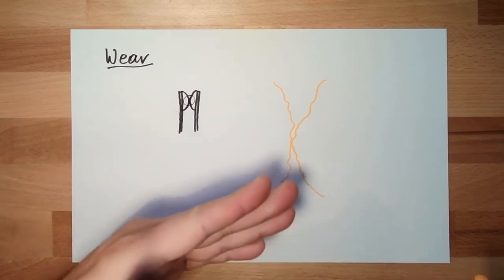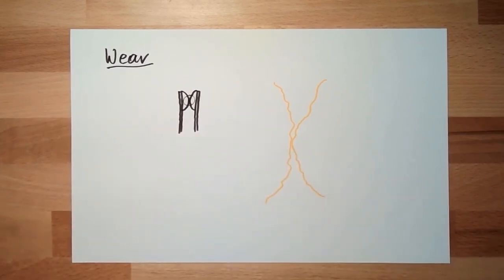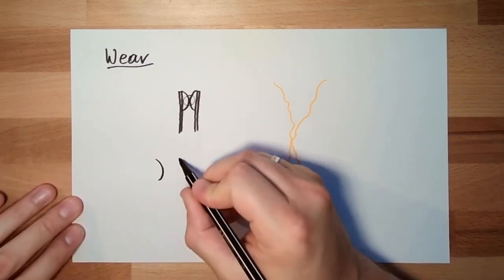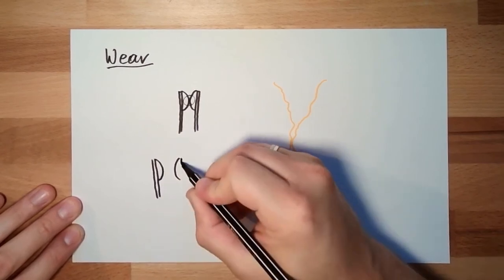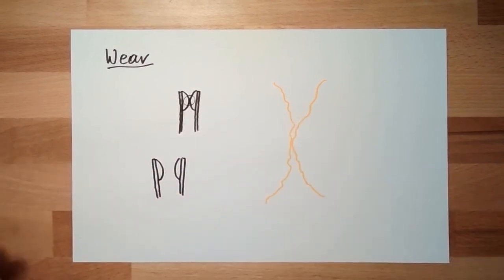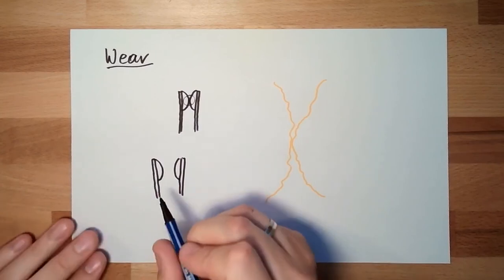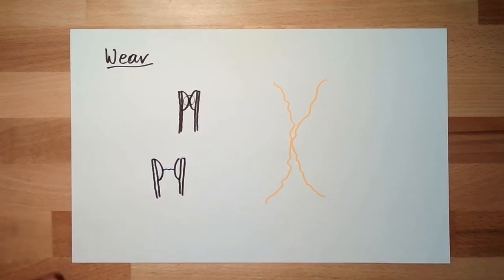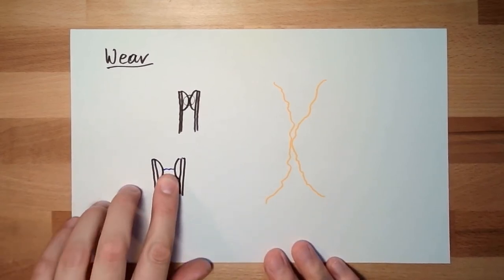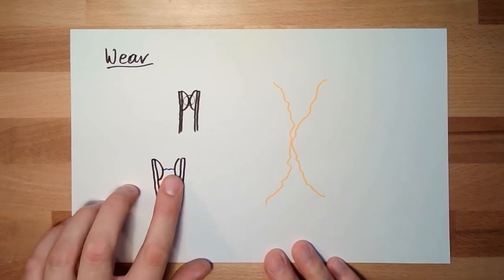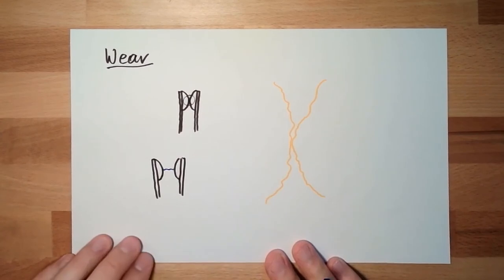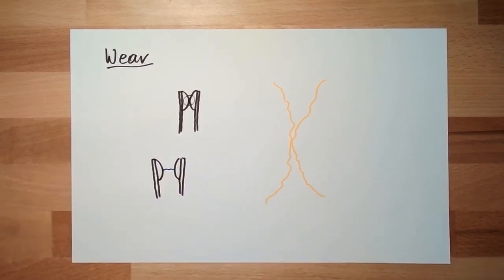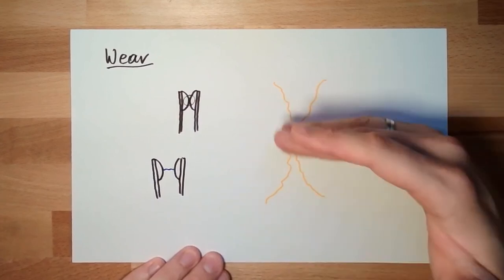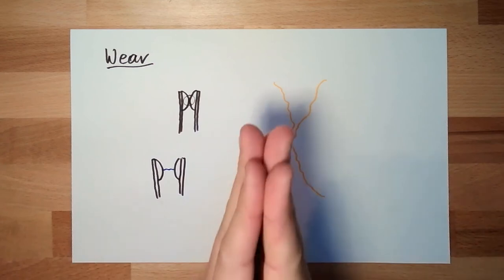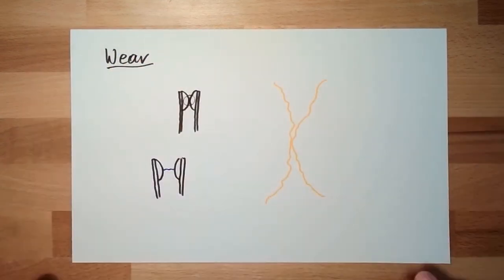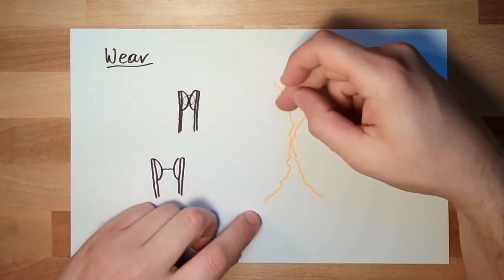Why does it look that awful, let's say? Because every time those two open, the current will not just be stopped. There is usually some small flash inside, some spark. And this spark can get really hot. It's not extremely hot overall, but it is a very local thing. So it will burn, melt a portion of the contact, and this will just drip off. And every time this is closing and opening, closing and opening, then we do have a small burnout here.